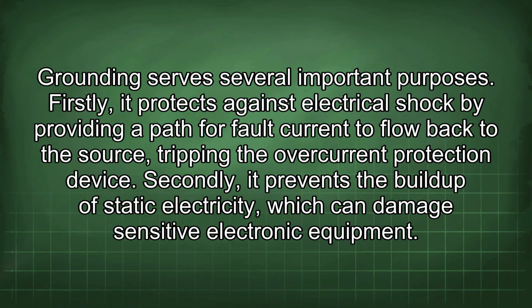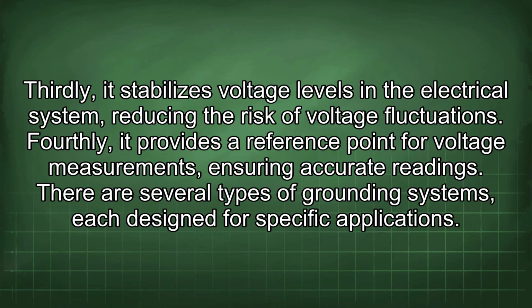Grounding serves several important purposes. Firstly, it protects against electrical shock by providing a path for fault current to flow back to the source, tripping the overcurrent protection device. Secondly, it prevents the buildup of static electricity, which can damage sensitive electronic equipment. Thirdly, it stabilizes voltage levels in the electrical system, reducing the risk of voltage fluctuations. Fourthly, it provides a reference point for voltage measurements, ensuring accurate readings.